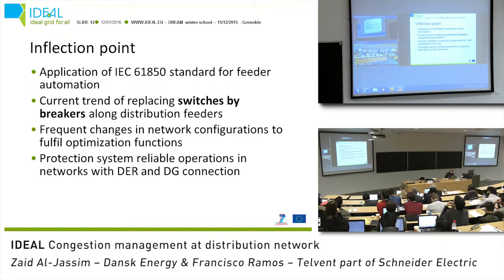So what pushed us to go in this direction? First of all, the application of the 61850 standard for feeder automation. And one thing that pushed us strongly is the current trend of replacing switches by breakers along distribution feeders, and of course the frequent change in network configuration.